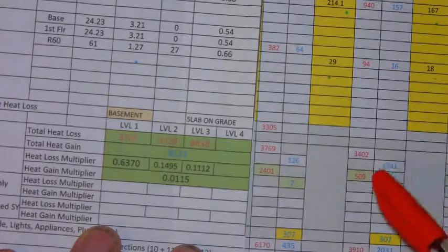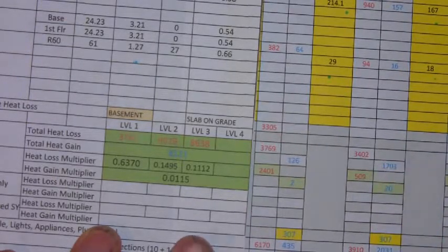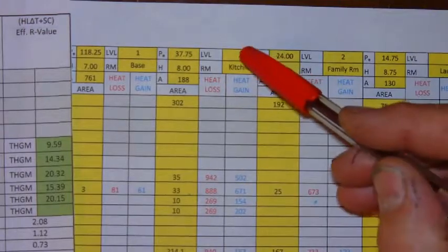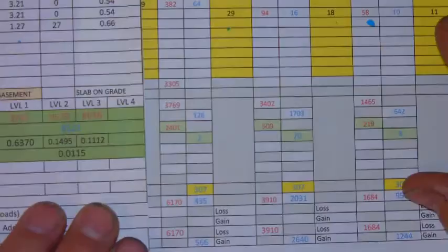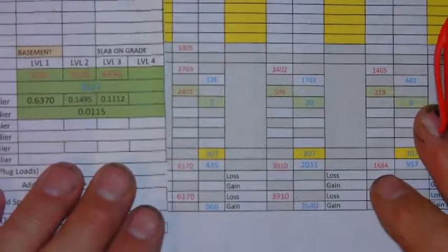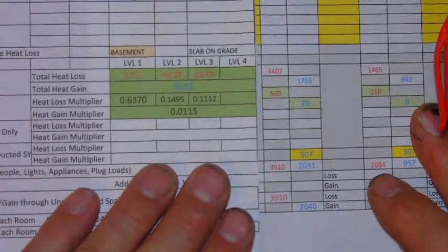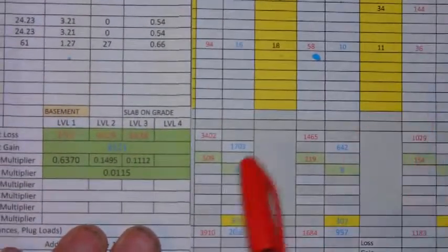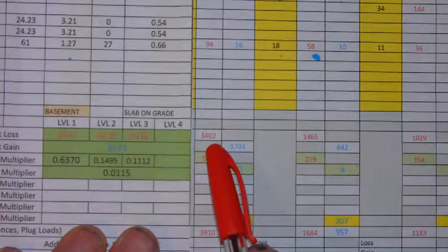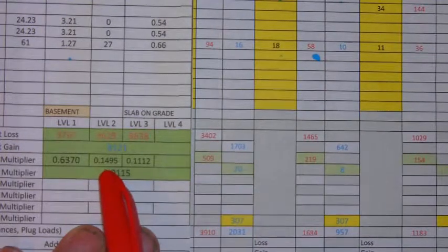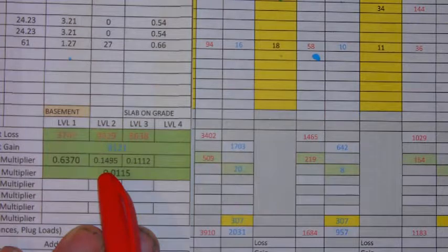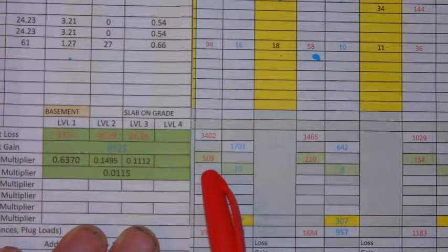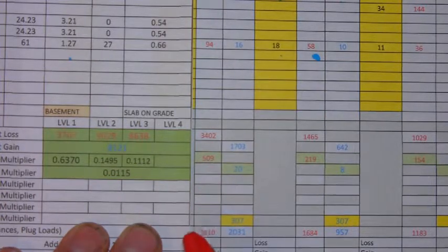For the kitchen, the kitchen is in level two. So you're going to use the level two multiplier. And so, we've got 3402 times the level two multiplier 0.1495, and that gives us 509 BTUs.